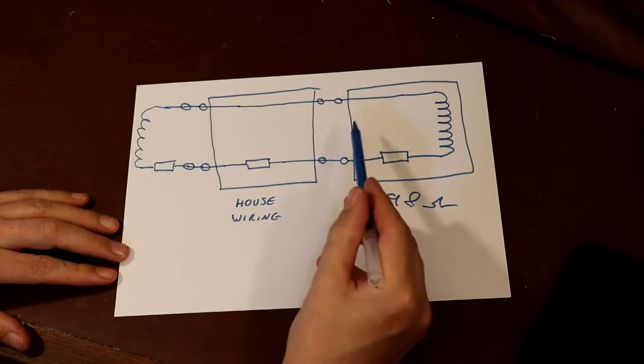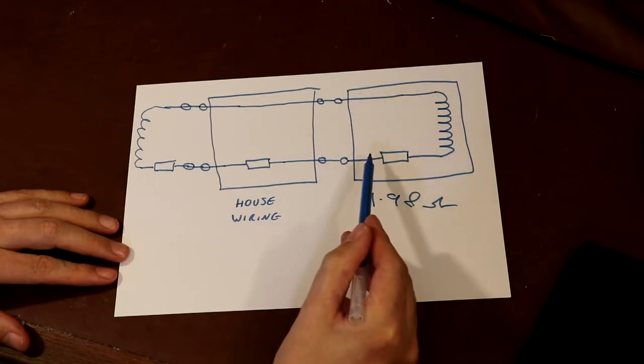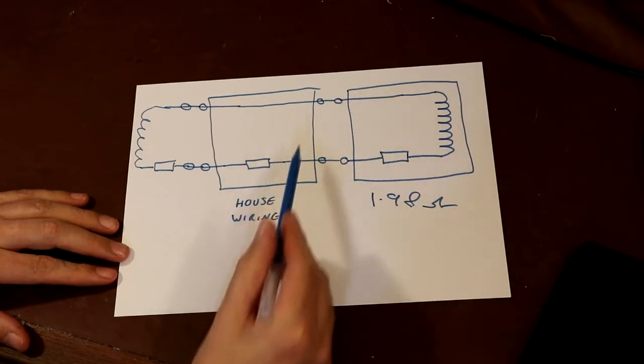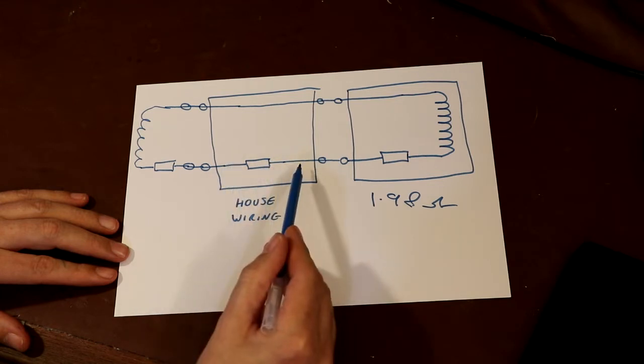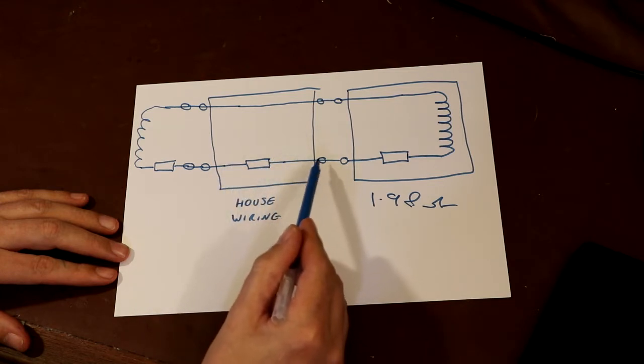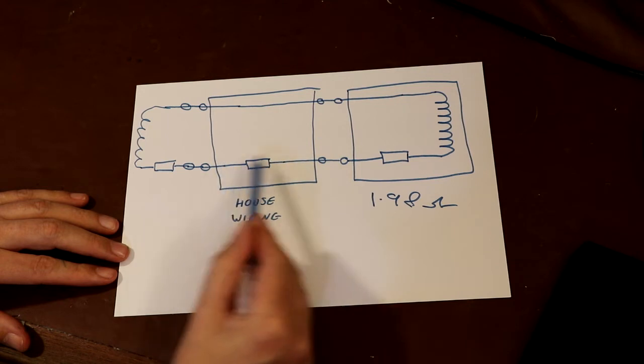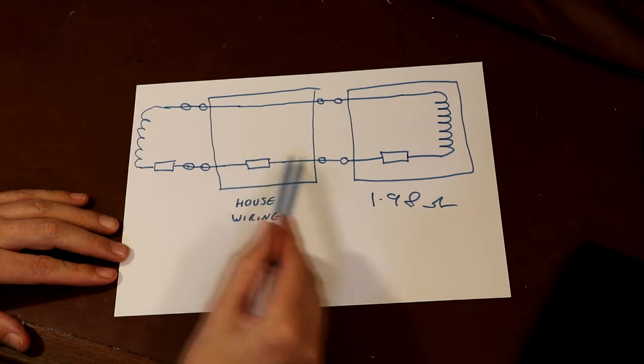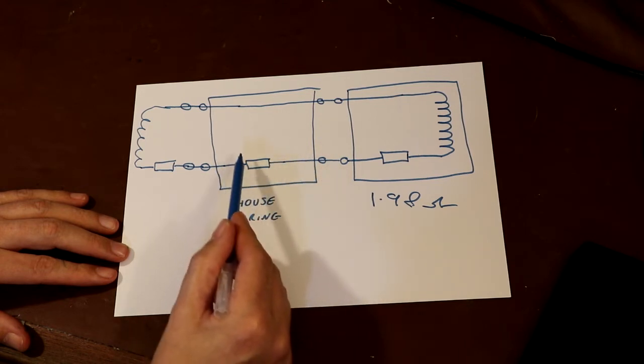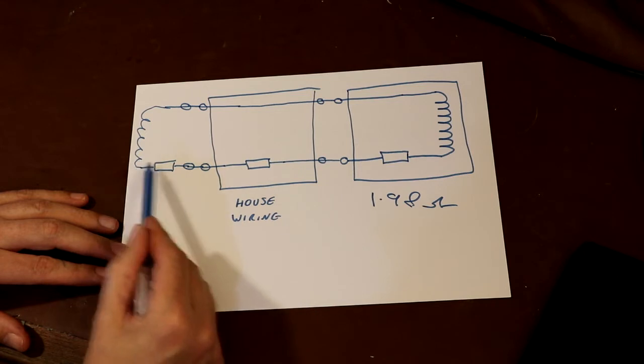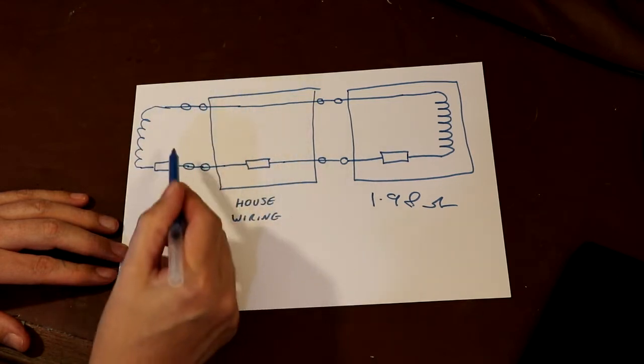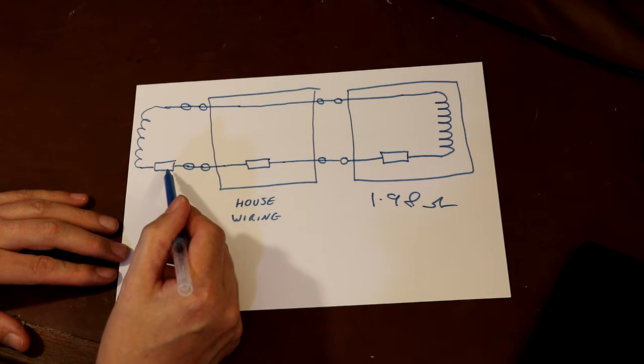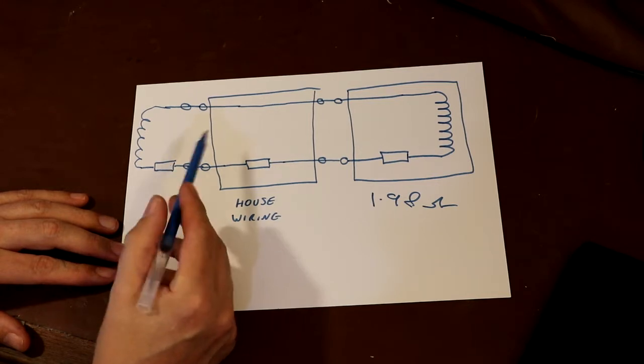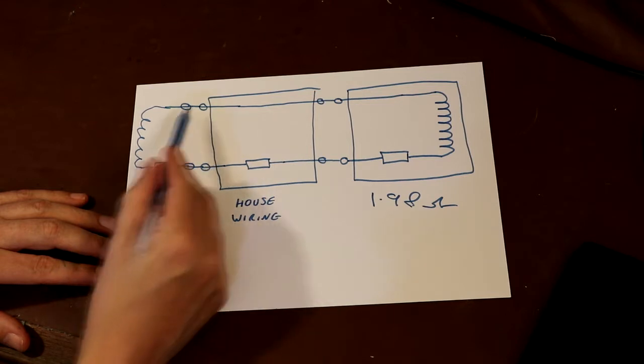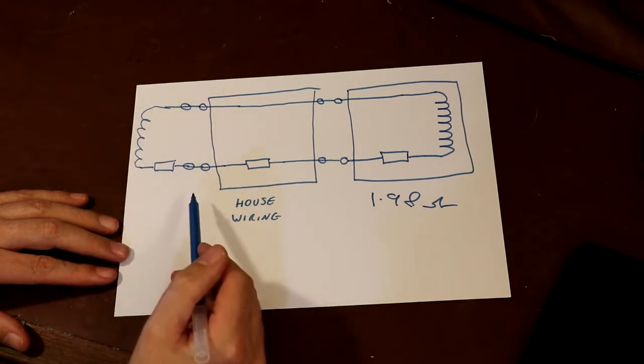So now that we know the resistance of our transformer and its connecting windings, the bit that we don't know is the supply impedance. So we've got the internal wiring in my house first of all, that's going to have a resistance to it, and then we're going to have a resistance back to the, I don't know, I live out in the country here, so we've got these big transformers that are strapped to the sides of telegraph poles. They call them pole pigs in America. So we've also got the supply impedance back to the pole pig.